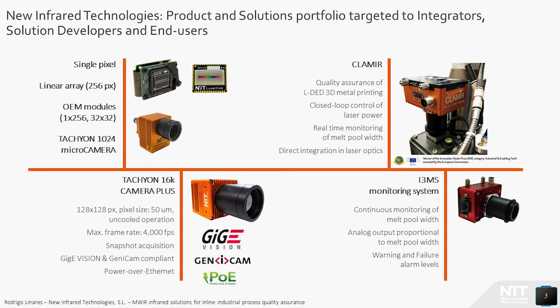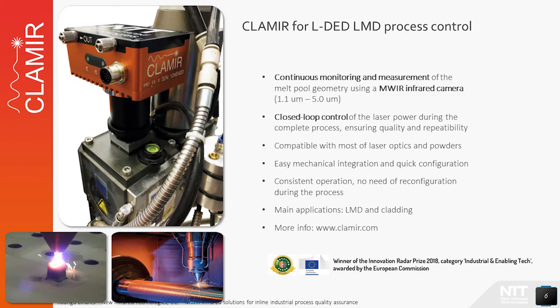Regarding the industrial solutions, we find CLAMIR and i3MS. Both are embedded systems which operate in standalone mode with no need for a permanent connection to a PC. CLAMIR is designed for quality assurance of laser directed energy deposition processes, such as laser metal deposition or laser cladding, including EHLA high-speed cladding. CLAMIR is integrated directly in the laser optics, performs continuous monitoring of the melt-pool geometry, and controls the laser power in real time to prevent possible overheating of the part under manufacturing, improving efficiency and repeatability and avoiding unplanned production stops. CLAMIR has been awarded in 2018 by the European Commission with the Innovation Radar Prize in the category Industrial and Enabling Technology.